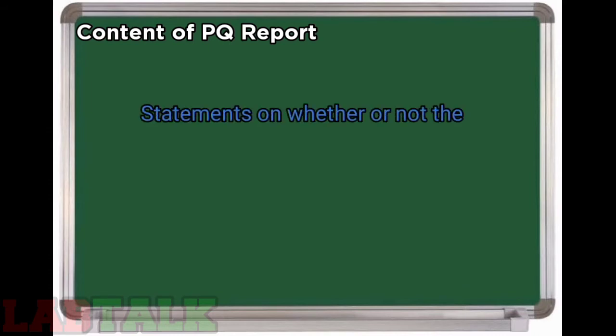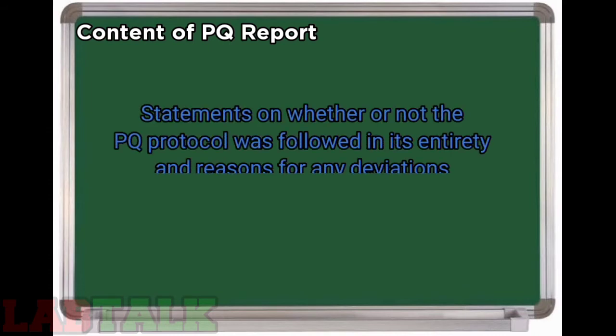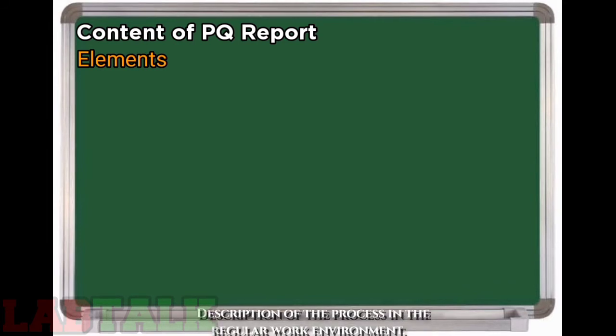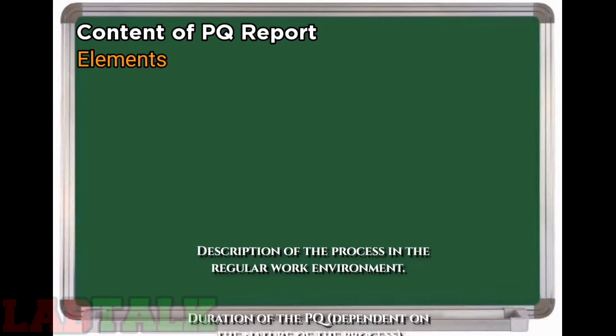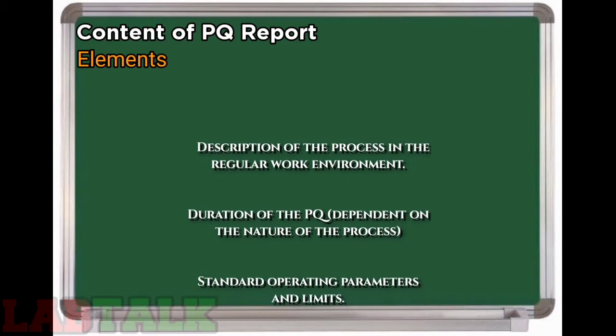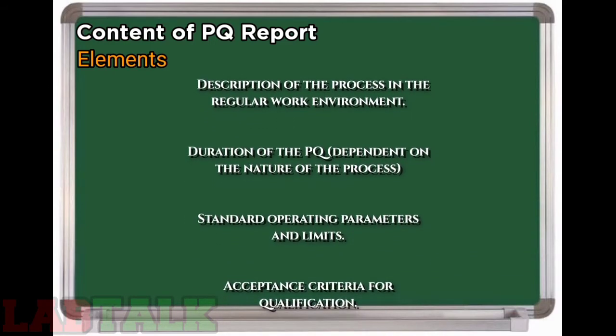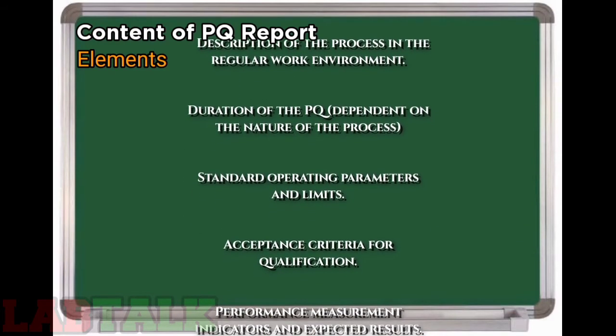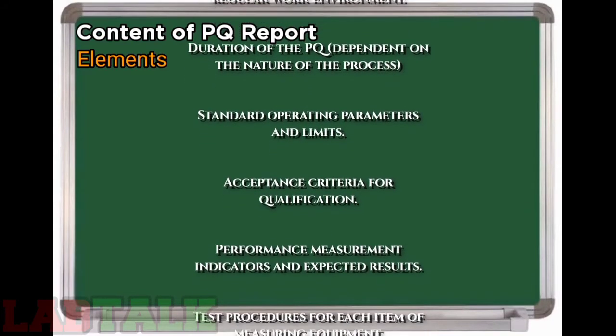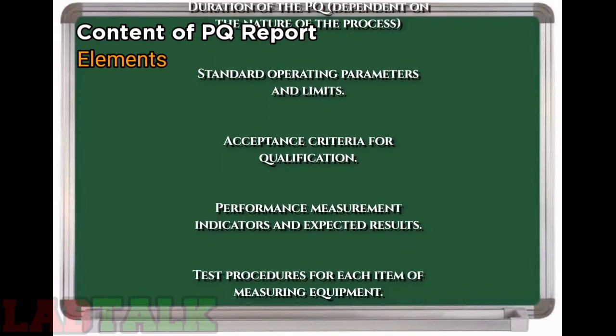Performance qualification report should include statements on whether or not the PQ protocol was followed in its entirety and reasons for any deviations. Elements that should be included in the PQ protocols are: description of the process in the regular work environment, duration of the PQ, standard operating parameters and limits, acceptance criteria for qualifications, performance measurements, indicators and expected results, test procedure for each item of measuring equipment, test data to be gathered, and the time frame and schedule for gathering data.